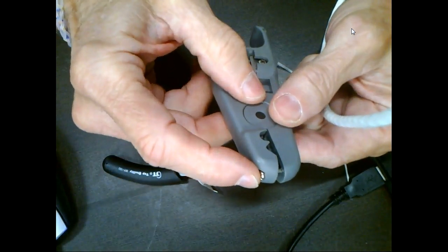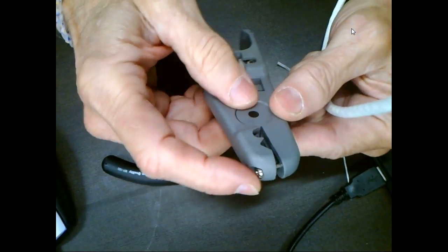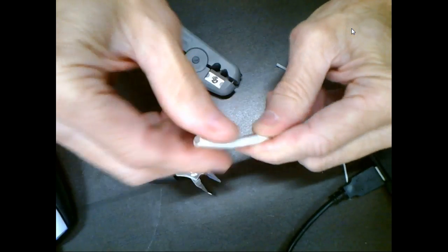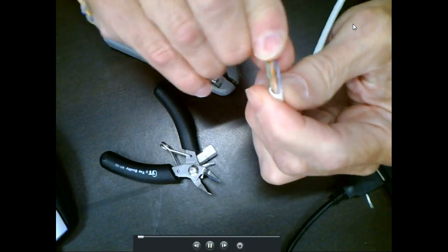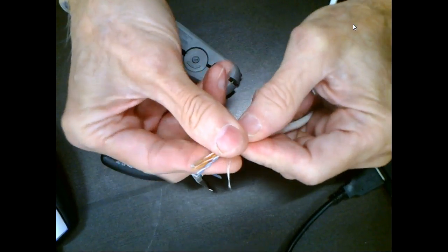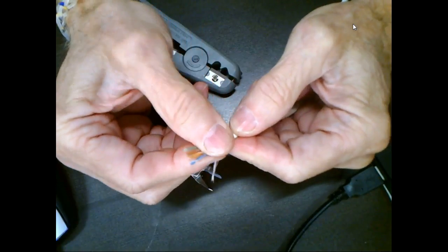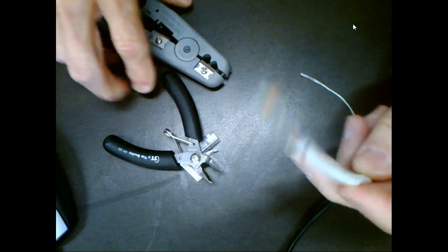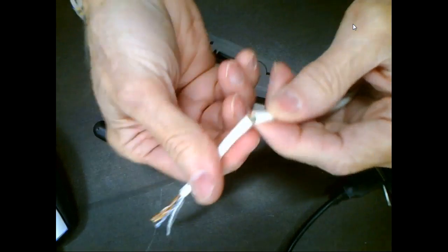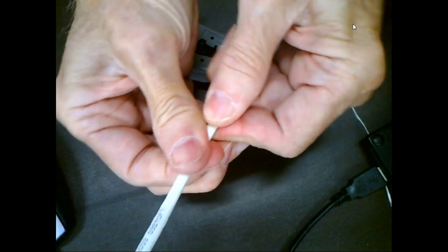But you can see these guys have adjustments on them, so you can set it correctly. We usually use the outside one. Just put it on there, spin it around, then move back and forth, break it off and pull it off. Come back and bend the wire over looking for copper. If we don't see copper, we're okay. You understand that? Like that slit? These are called cable strippers. Spin around and do what? Turn it back and forth, break it, and then pull it off. We're okay?